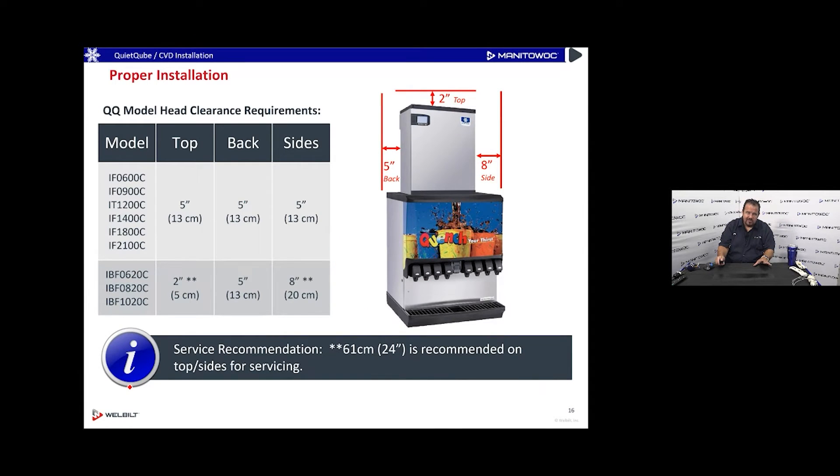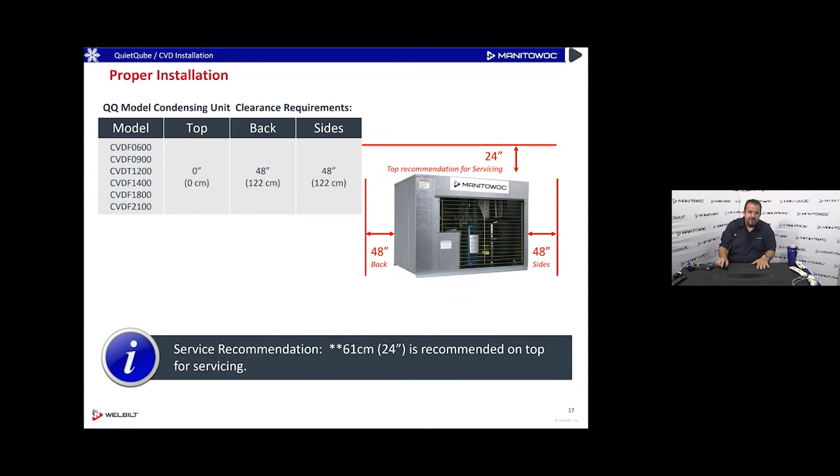For IBF units — perhaps in a drive-through — clearance requirements are five inches on the back, eight inches on the side, and two inches on the top. For the outdoor condenser, if roof space is at a premium and you're tempted to stack units, you need 24 inches of clearance on top, 48 inches on the back, and 48 inches on the side to let the condenser reject heat properly, especially in summer.